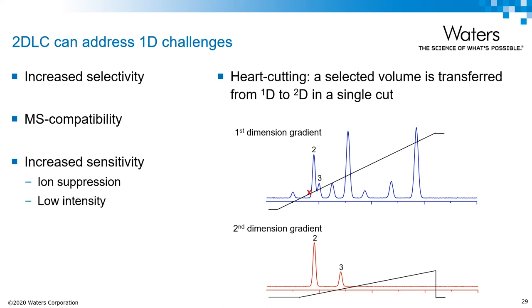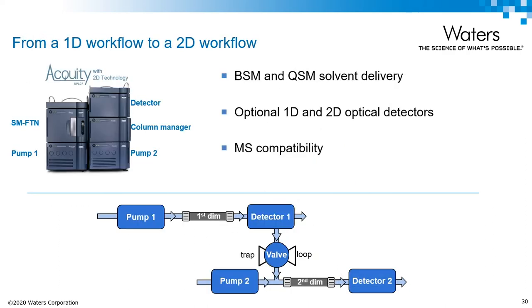Today we're going to focus on heart cut mode, which works to transfer discrete fractions to the second dimension for analysis. Peaks 2 and 3 are partially co-eluted in the first dimension, and by transferring them to the second dimension, we can tailor the second dimension gradient to further resolve them. This is in contrast to comprehensive 2DLC, which sends fractions of the entire 1D chromatogram to the second dimension. Although you can purchase a new system dedicated specifically to 2D, you can also transition your existing 1D workflow with a few module considerations. A secondary pump is incorporated for the second dimension separation, and the column manager must be equipped with valve switching functionality.